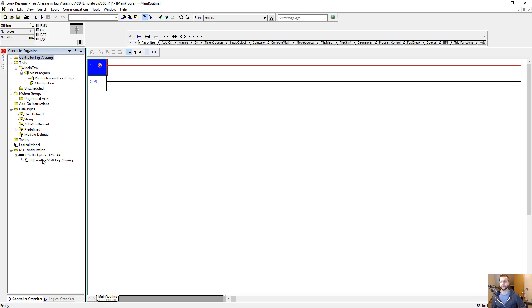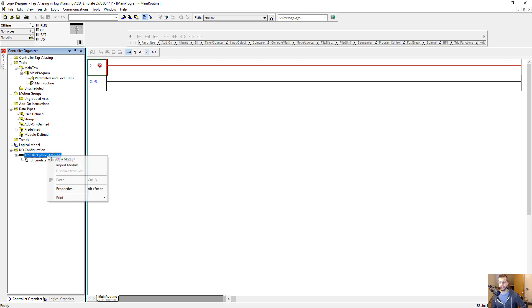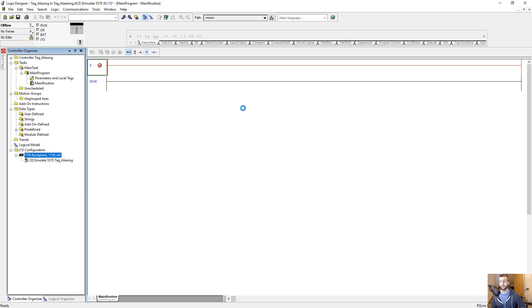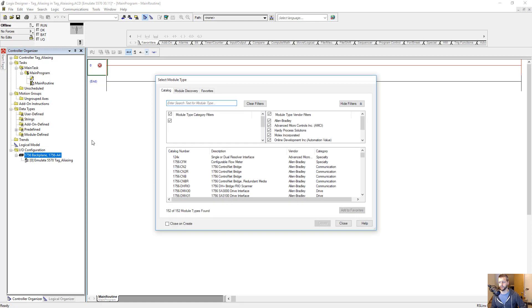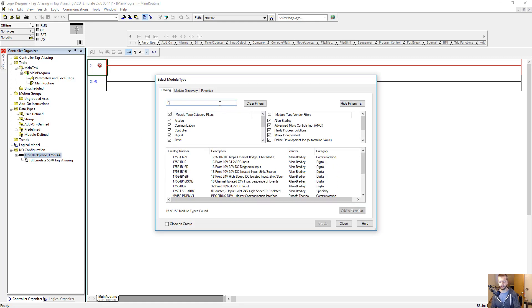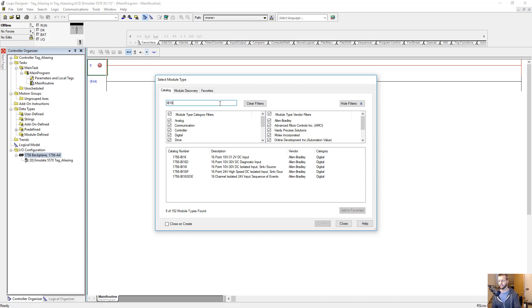We've got an emulate controller here — you could have any controller, but we've just got the emulate here. Let's go ahead and add a couple IO modules. First, let's do a discrete input module. This will need to be a ControlLogix type module since we're using the emulator controller. My favorite is the IB16, which is basically a 24-volt DC 16-point input. Let's grab that — just double-click it.